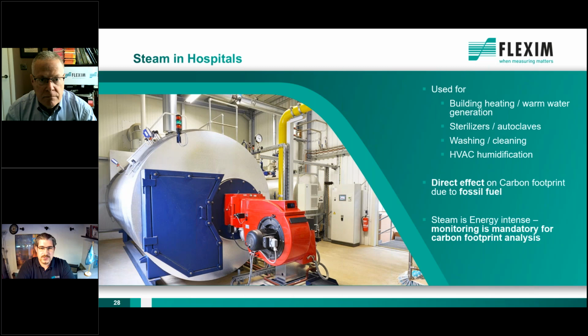investigations, because the thing with steam is, of course, especially in the hospital, is very widely used. So you use it for building heating, warm water generation, especially for the sterilizers and autoclaves, for washing, cleaning, for the HVAC humidification. But of course, the thing is here, basically or mostly you use gas, natural gas, to fire your boiler. And this is, of course, a direct effect of your carbon footprint. You will use a lot of natural fossil fuel, which directly produces a lot of CO2. So this is why steam is, for one, energy intensive, and secondly, a direct effect on your carbon footprint. So it should be very much mandatory to monitor your steam flow for your carbon footprint analysis.